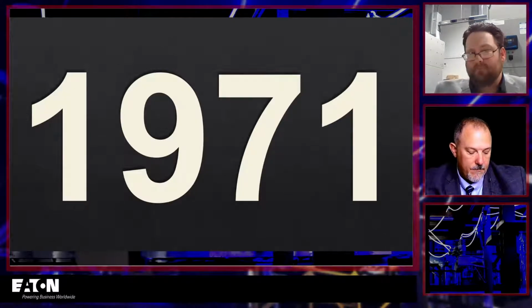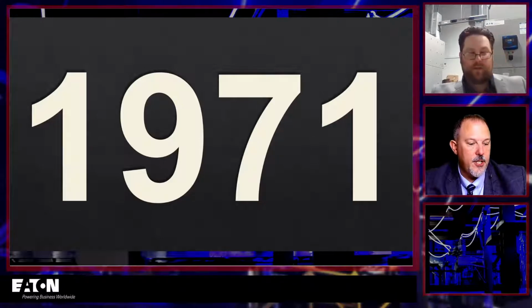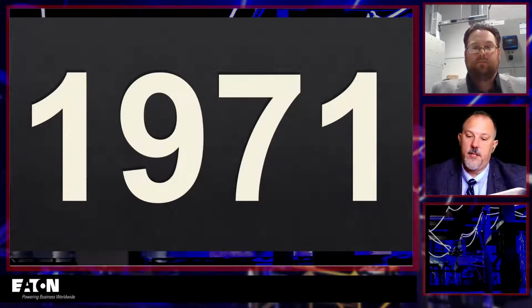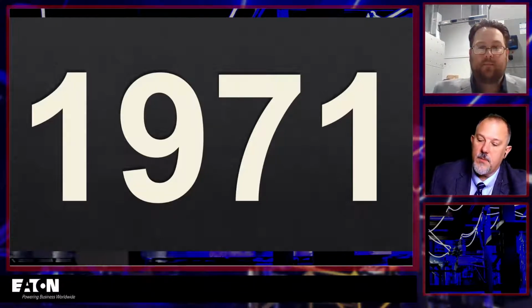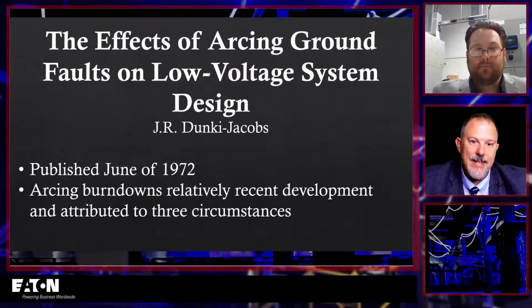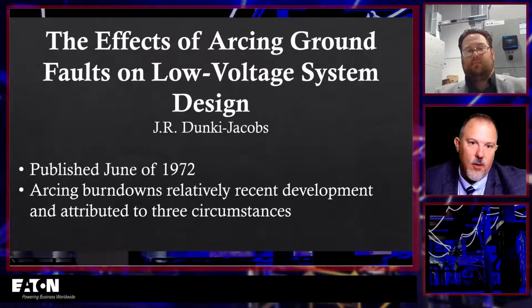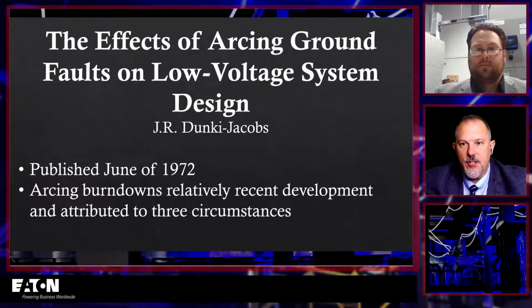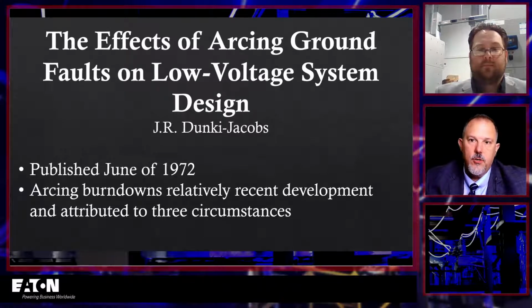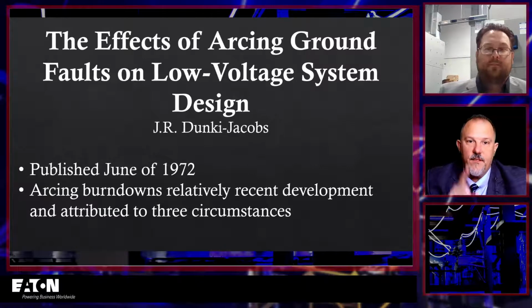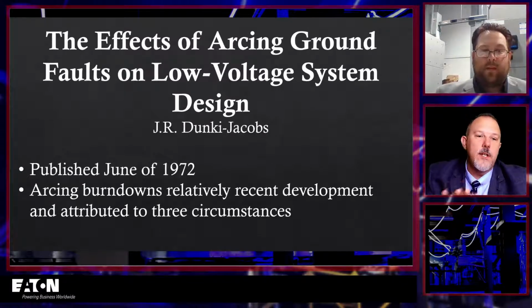Now, that's the panel recommendation. The submitter was NEMA, the National Electrical Manufacturers Association. And it says the purpose of this proposal is to require ground fault protection of low voltage electrical distribution systems in order to minimize chances of injury of personnel and reduce damage to equipment. And I'll tell you what was going on in 1970 going into the 70s. I did a lot of research on this because I really wanted to understand what David Englehart was asking. If you look back at some published IEEE papers, Dunki-Jacobs was an author who did a lot of testing in this area, and he published The Effects of Arcing Ground Faults on Low Voltage System Design, because here is what was going on. And he laid it out really nice in this paper.